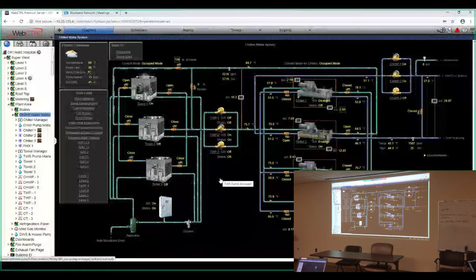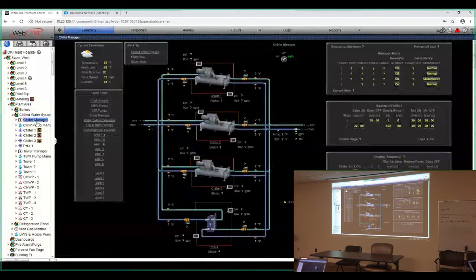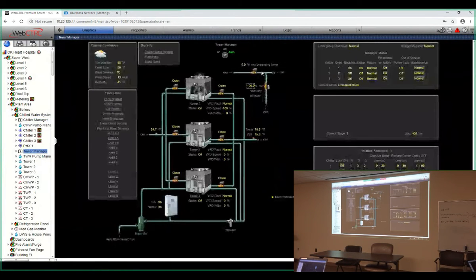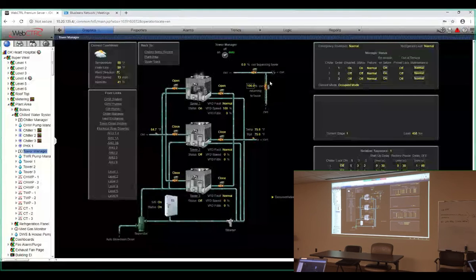Talk to us about how you're controlling the bypassing valve of the tower. Okay, tower bypass. It's actually on the tower manager. So we're trying to maintain that 75-degree set point on those towers. As we get below that set point, we'll start bypassing the tower and recirculating the water back to the chiller. You're going to see that when we come out of that free cooling mode. We're trying to get water warm back up going to those chillers.